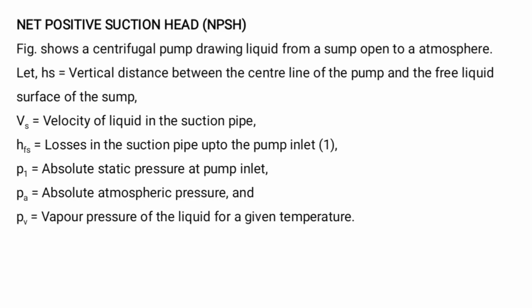Suction head is the vertical distance between the center line of the pump and the free liquid surface of the sump. From the sump level to the center line of the pump is known as suction head. The velocity of the liquid in the suction head is known as suction head velocity, Vs. Then HFS is equal to losses in the suction pipe up to the pump inlet.